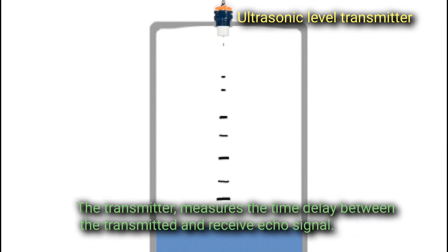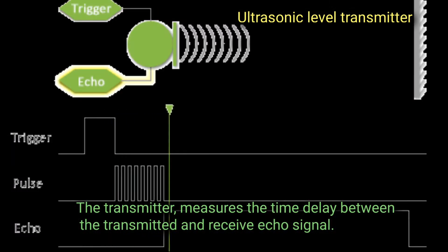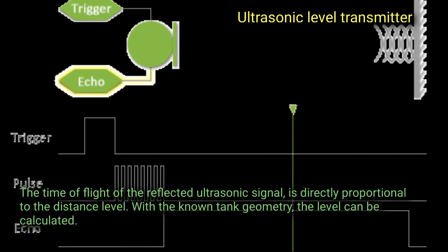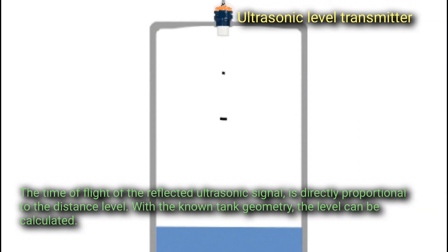The transmitter measures the time delay between the transmitted and received echo signal. The time of flight of the reflected ultrasonic signal is directly proportional to the distance levels. With the known tank geometry, the level can be calculated.